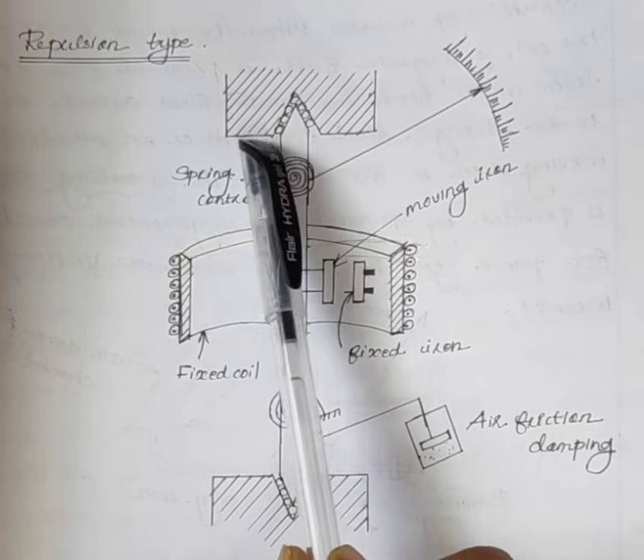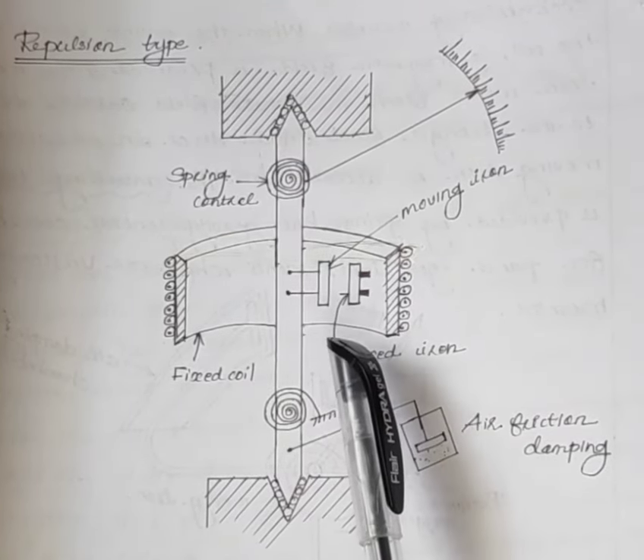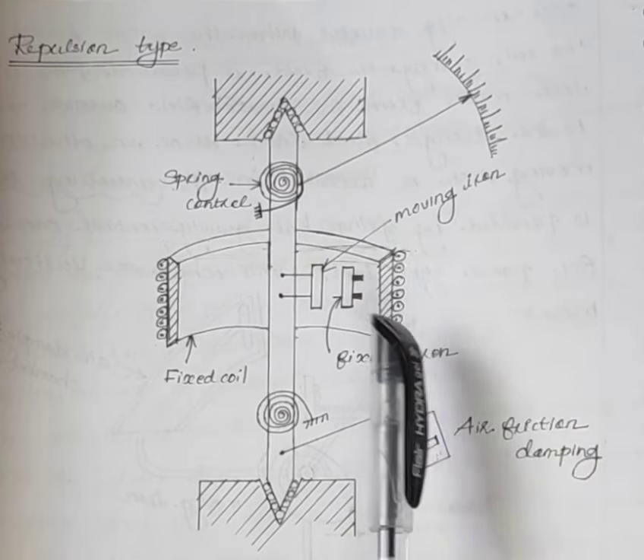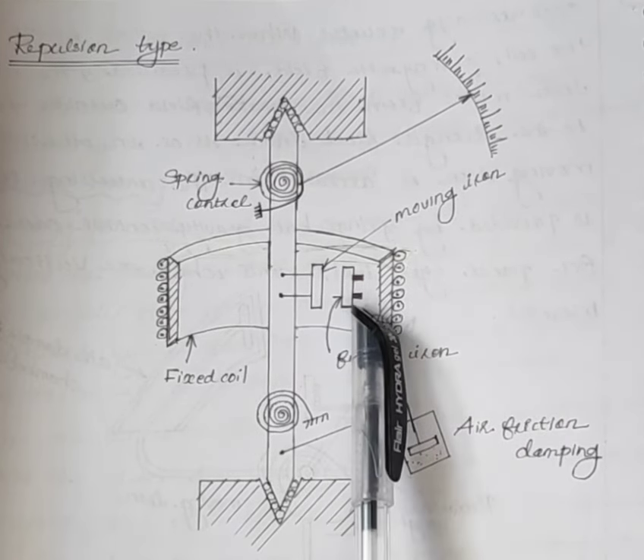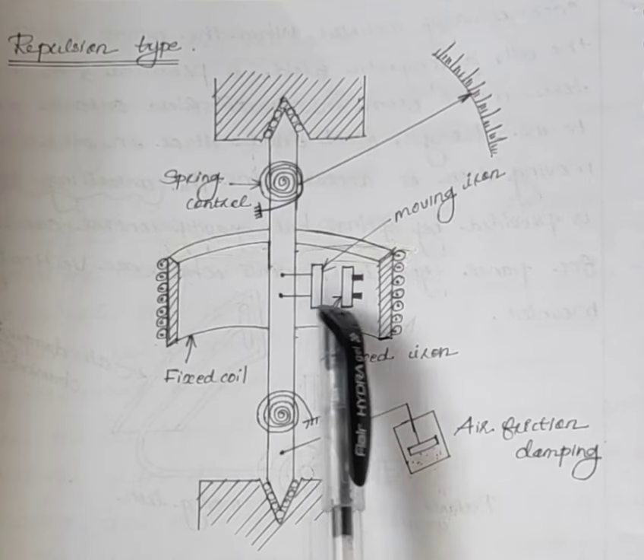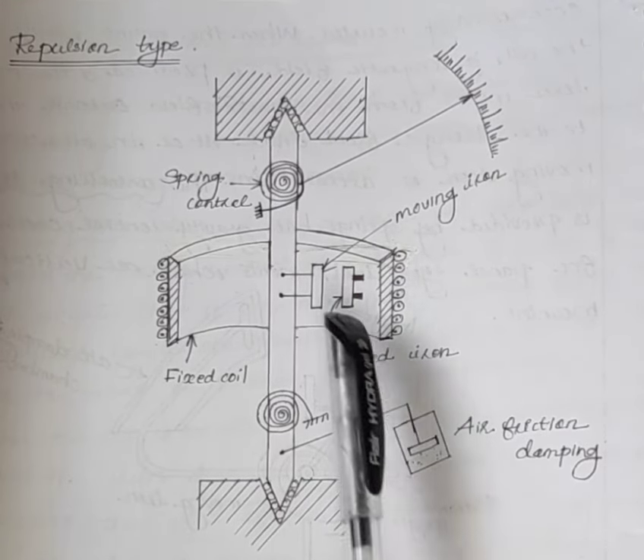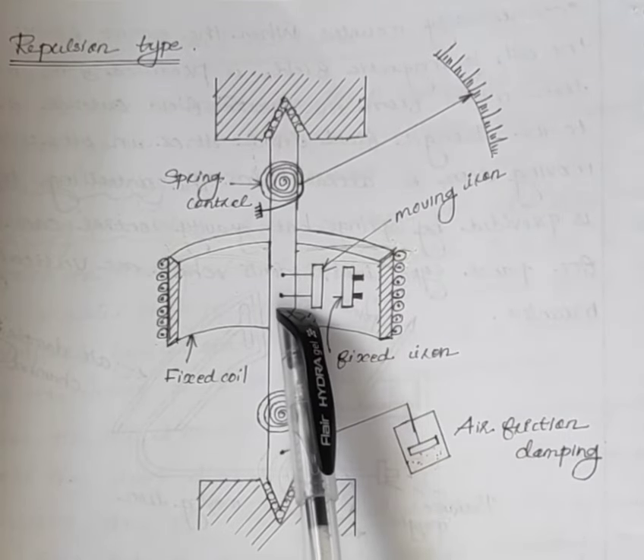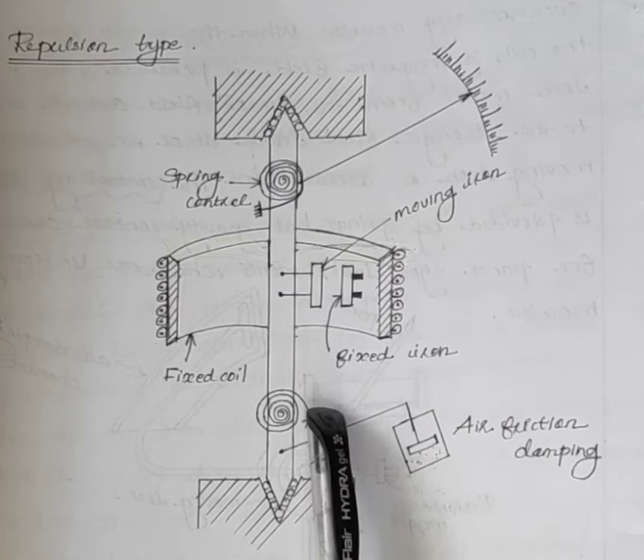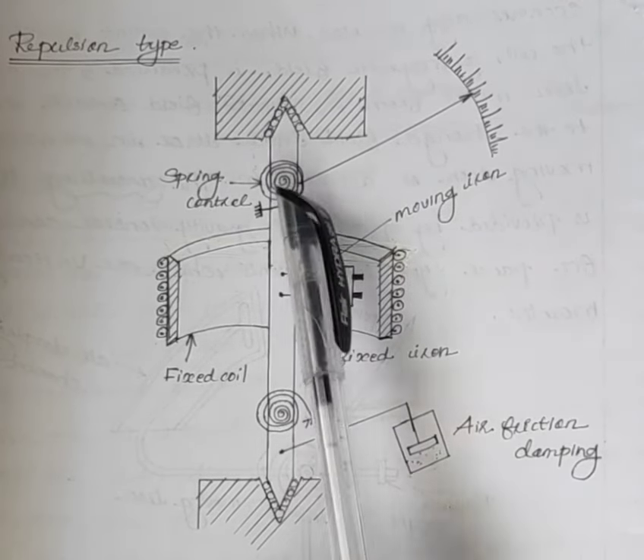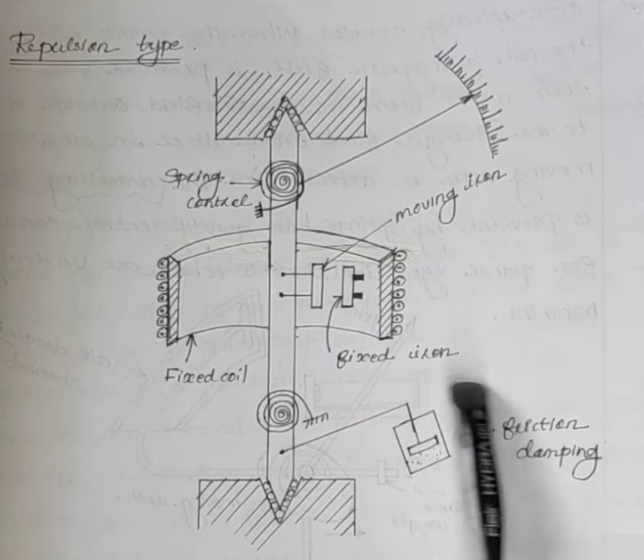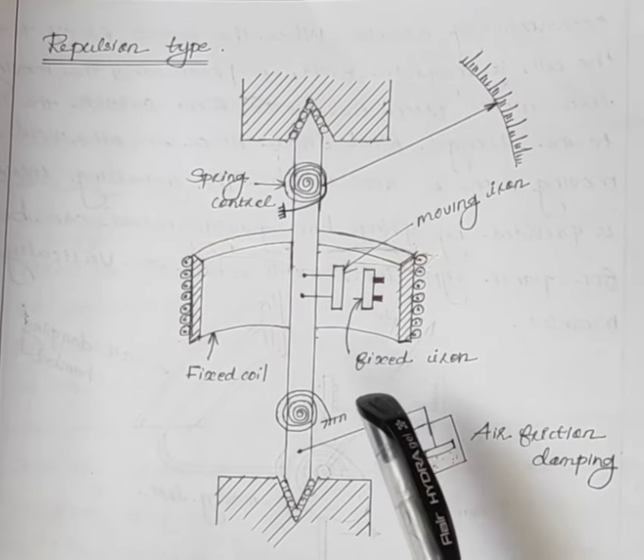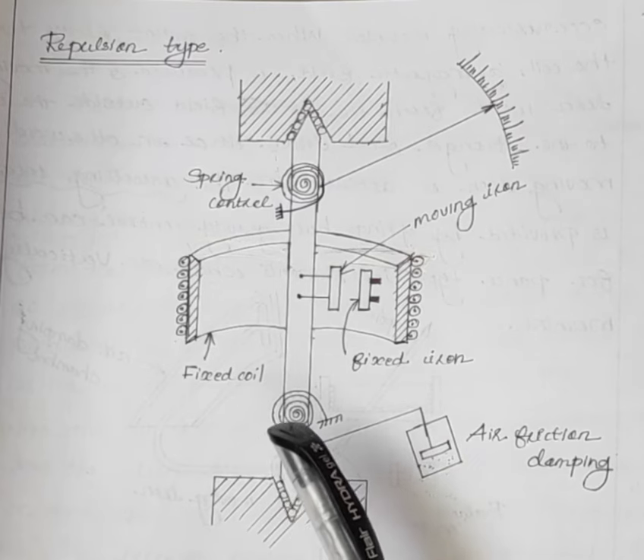Next is the repulsion type moving iron instrument. Here the stationary coil acts as an electromagnet, and the instrument has two iron plates — one is fixed and another one is movable, which is attached to the moving system. The controlling torque is provided by spring control; two springs are used. The damping torque is provided by air friction damping.